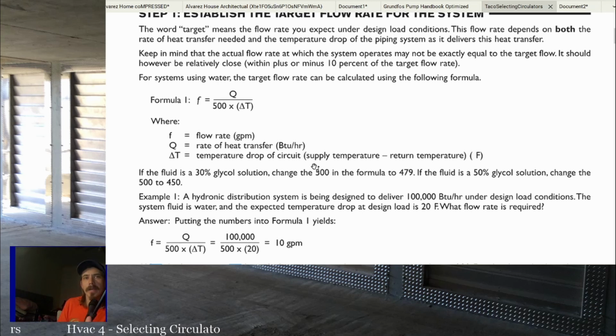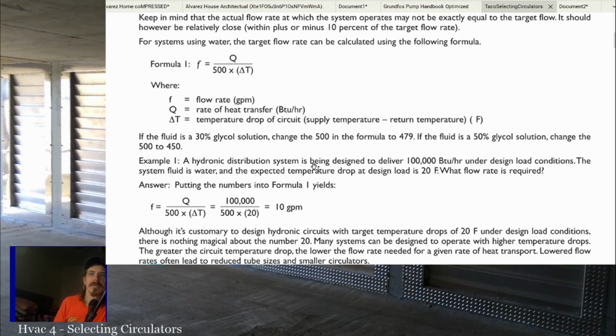So if you got glycol in the system, it actually does not transfer heat as efficiently as water does. So pure water always transfers heat better. But obviously, if you got glycol, it's there to protect it from freezing. So a lot of times you'll be between a 30 and 50% glycol solution to keep the system from freezing in case it comes in contact with really cold temperatures. So the reason that number changed is because 500 is basically a constant for how well the fluid is transferring heat, and the more glycol you have, the slightly less efficient that fluid will be at transferring heat.